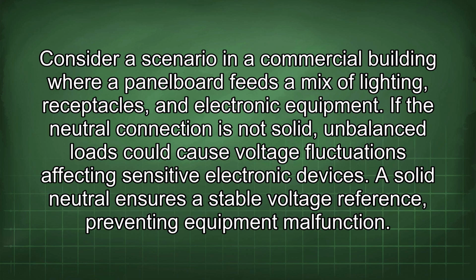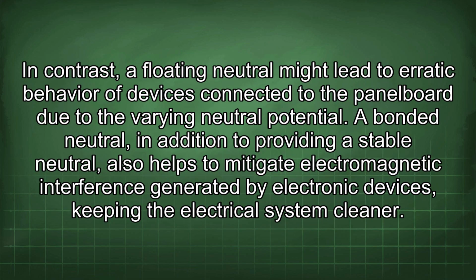If the neutral connection is not solid, unbalanced loads could cause voltage fluctuations affecting sensitive electronic devices. A solid neutral ensures a stable voltage reference, preventing equipment malfunction. In contrast, a floating neutral might lead to erratic behavior of devices connected to the panel board due to the varying neutral potential. A bonded neutral, in addition to providing a stable neutral, also helps to mitigate electromagnetic interference generated by electronic devices, keeping the electrical system cleaner.